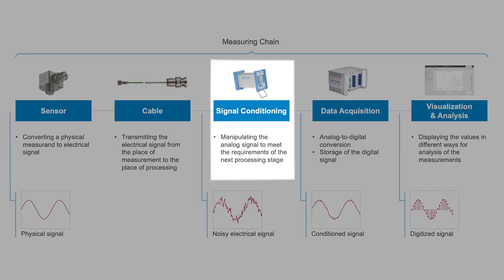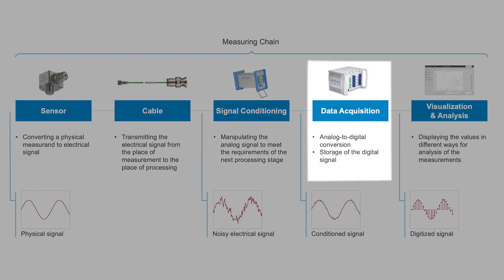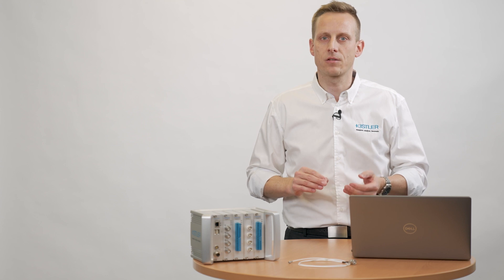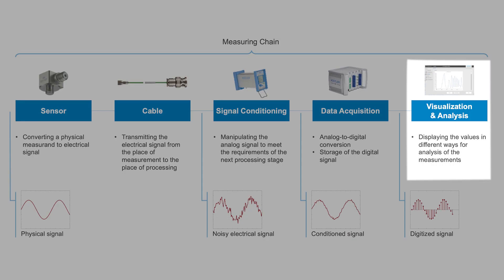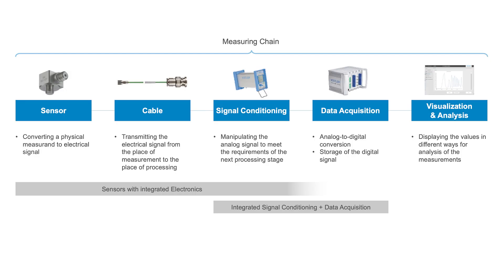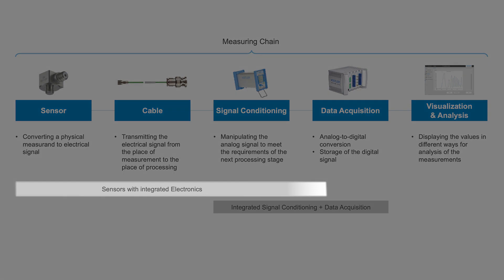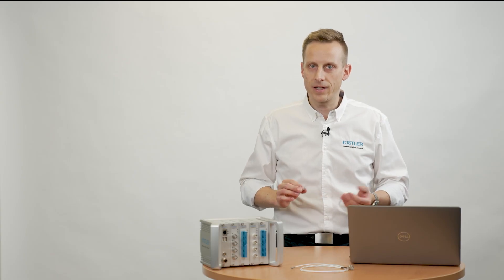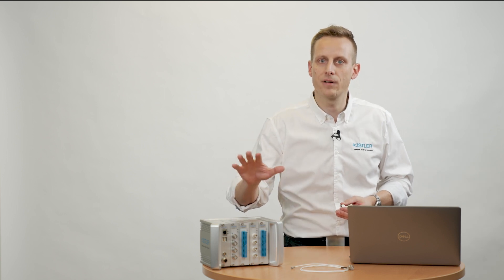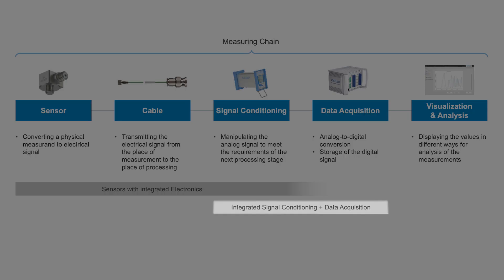The signal conditioning stage is used to transform the analog signal before converting it to digital. This normally includes amplification and filtering. The data acquisition converts the analog input signal into digital values and stores it for further processing. Visualization and analysis is the actual goal of the measurement. Depending on the measurement and application, sensors with integrated electronics are available — with that, additional signal conditioning or even digitalization may become obsolete. Very common today is that data acquisition devices already include a full signal conditioning stage, but there are still cases with special requirements where an external signal conditioning can make sense.